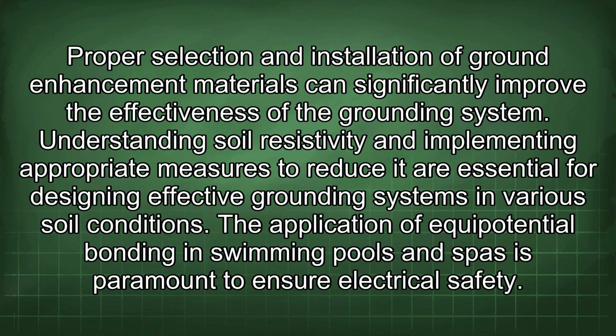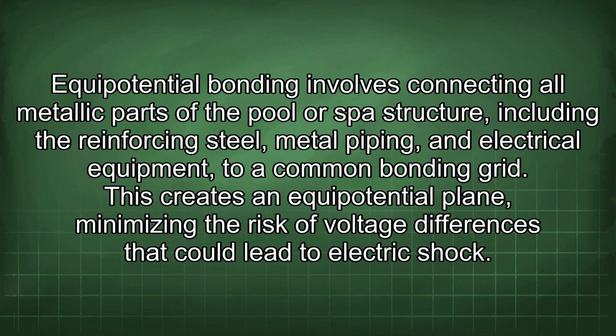The application of equipotential bonding in swimming pools and spas is paramount to ensure electrical safety. Equipotential bonding involves connecting all metallic parts of the pool or spa structure, including the reinforcing steel, metal piping, and electrical equipment, to a common bonding grid. This creates an equipotential plane, minimizing the risk of voltage differences that could lead to electric shock.